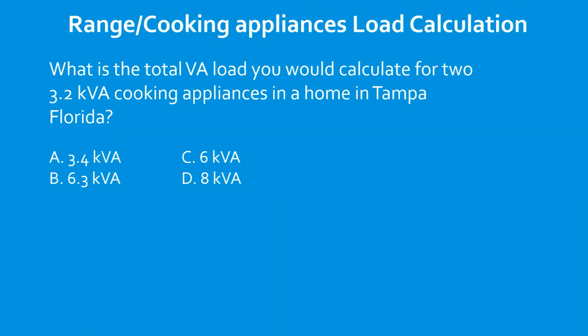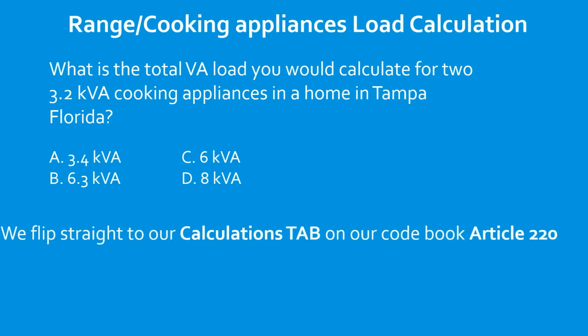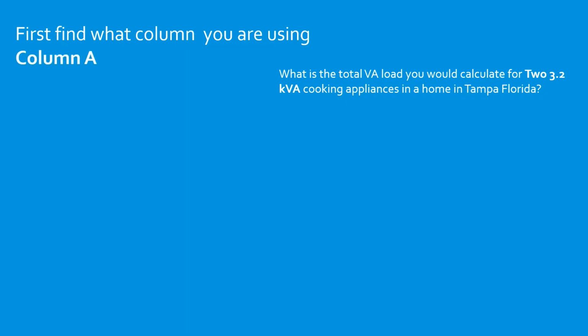Great job. What is the total VA load you would calculate for 2 3.2 kVA cooking appliances in a home in Tampa, Florida? So we're going to flip straight to our calculations tab, straight to Article 220. We're pros, so we're going to head straight to Table 220.55 because this is a range question. Now we're going to figure out what column we're using. Reread your question. What is the total VA you would calculate for 2 3.2 kVA cooking appliances? So we know now that we're going to be in column A because we're less than 3.5.